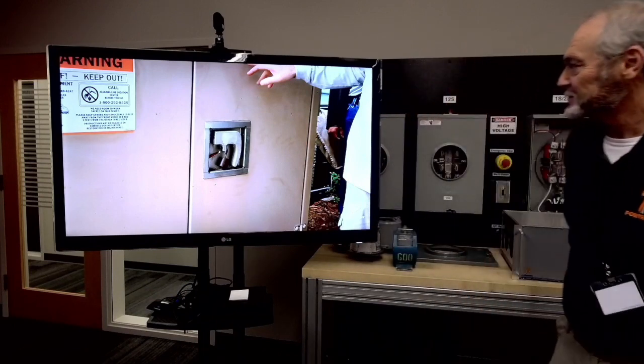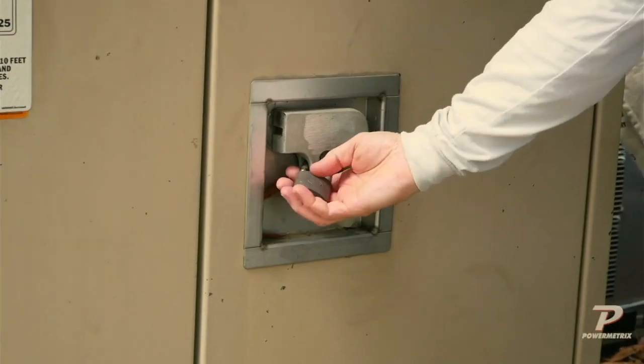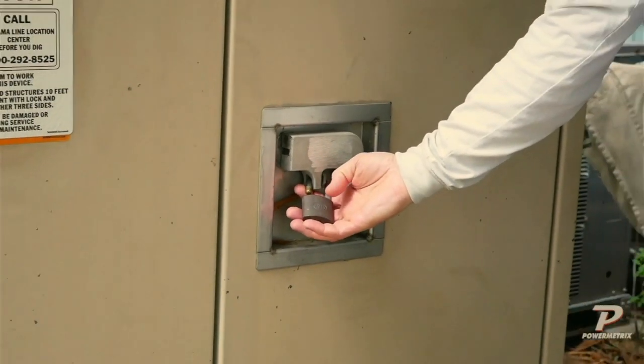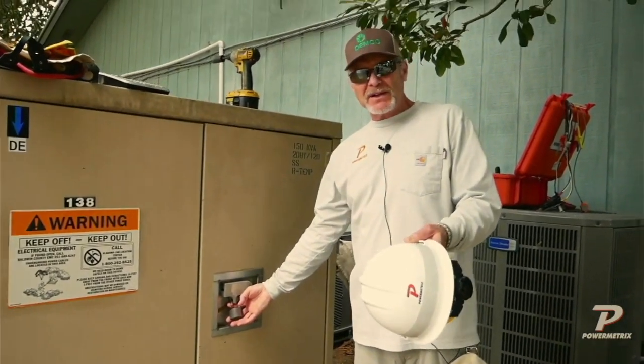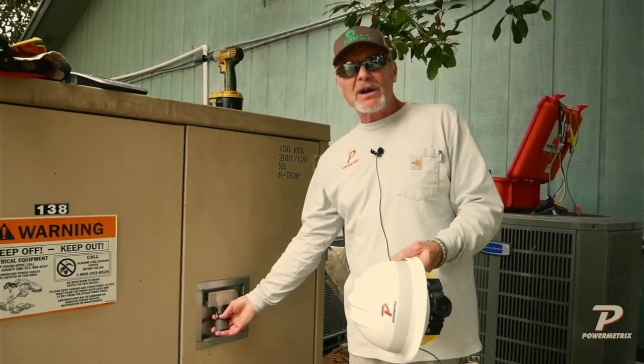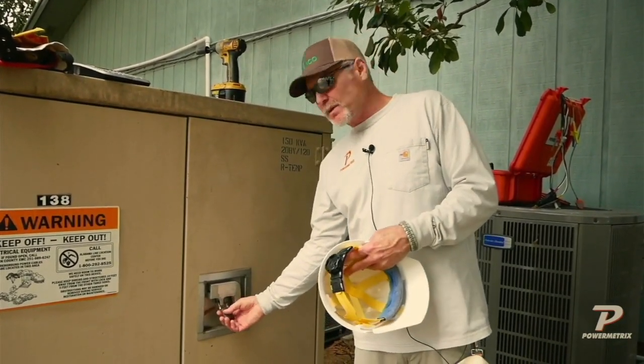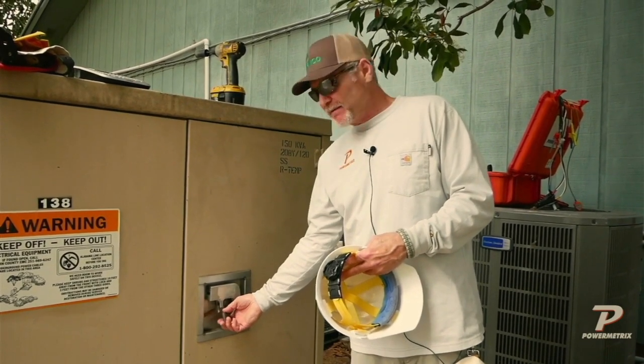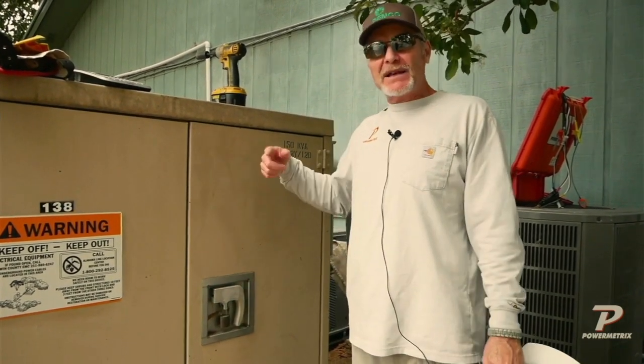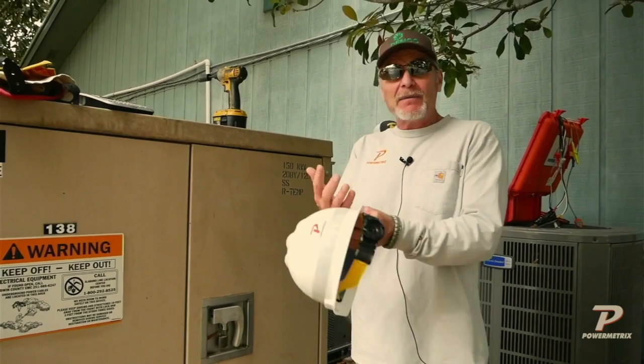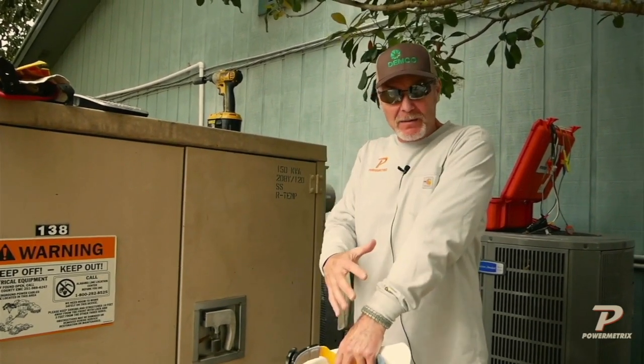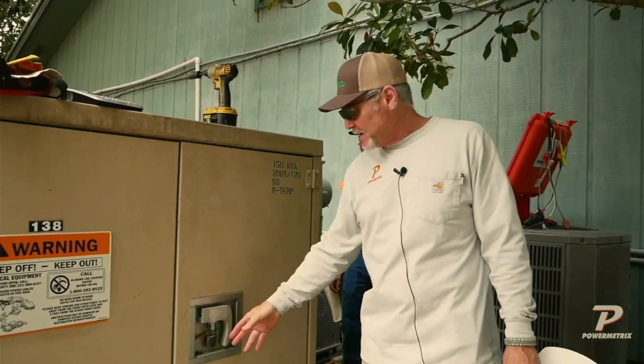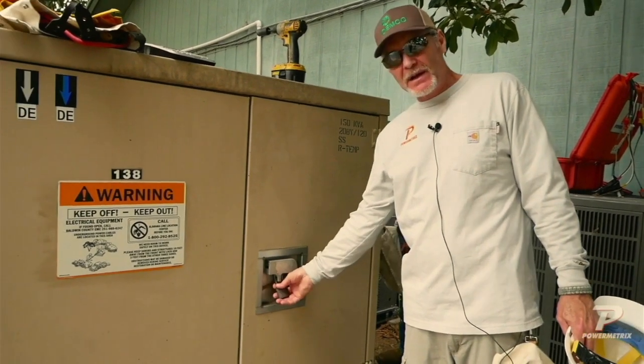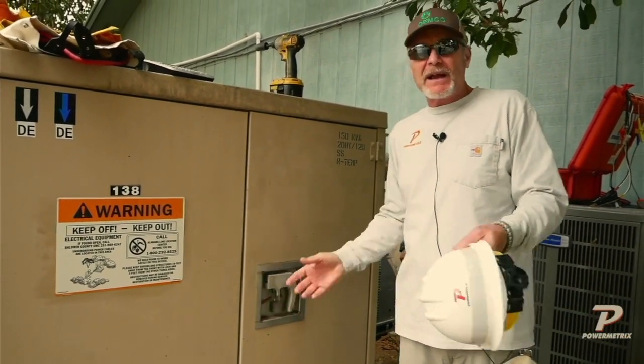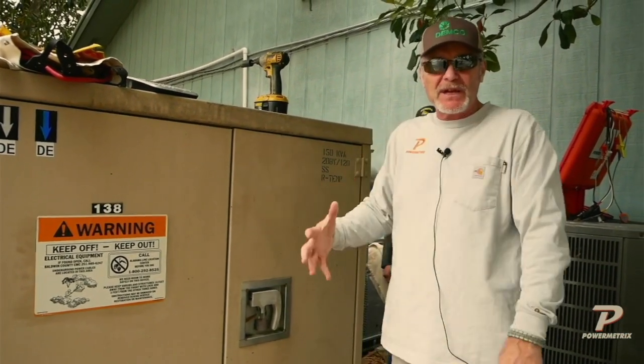You've got a secondary lock here on the outside. With the secondary lock and that level of security, you don't have to have your primary protection on when just working with it. Once I get past that into the primary, I need my primary gloves on and be sleeved up because I'm going inside it. But to just take this padlock off, that's secondary, so I can do that without all the primary gloves, sleeves, and protection on.